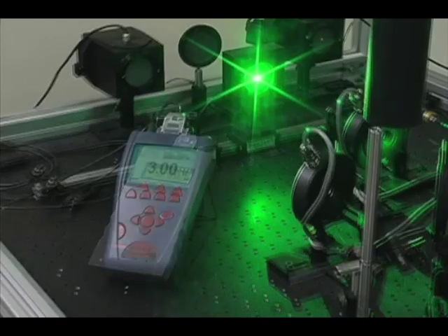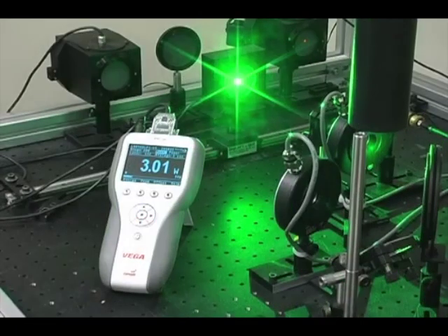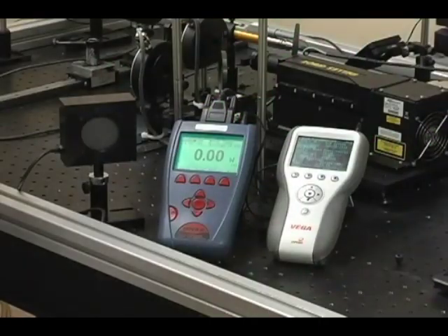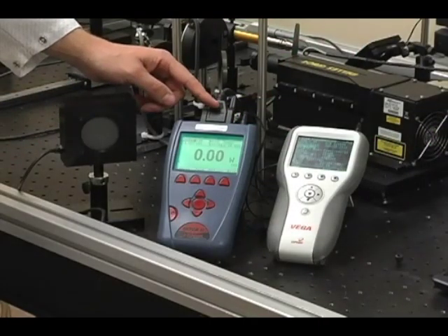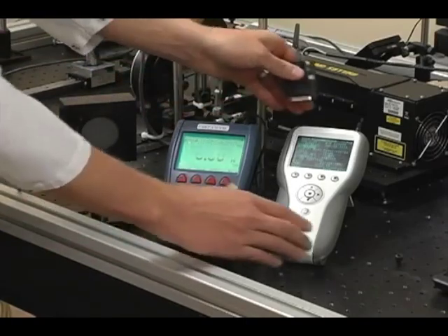These sensor-meter combinations are completely plug and play. The identity and calibration for each sensor is stored in its smart head connector, so the information moves with the sensor and any sensor will work with any meter.